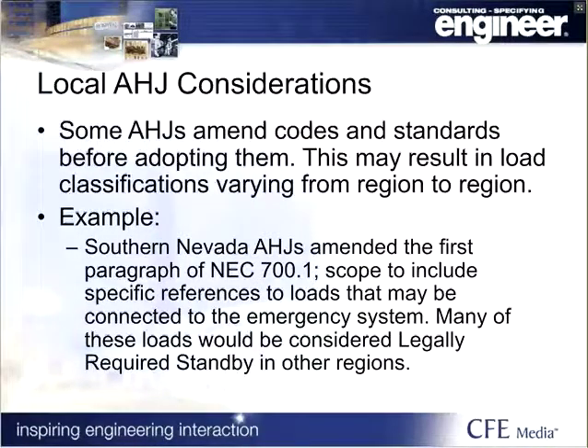When determining what loads to connect to each system, it is important to consider the project location and any locally adopted codes. Many AHJs opt to amend codes prior to adoption. An excellent example of this is in Southern Nevada. AHJs in this area have amended the first paragraph of NEC 700.1, which identifies the scope of the emergency systems article. They added verbiage identifying specific loads that may be connected to the emergency system.